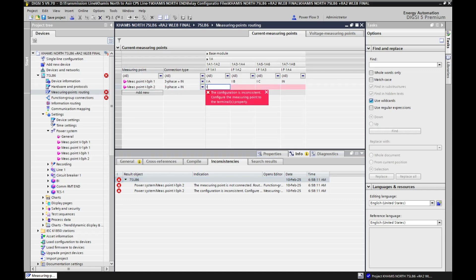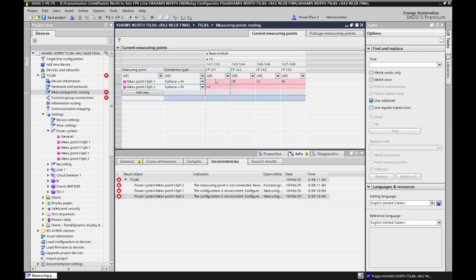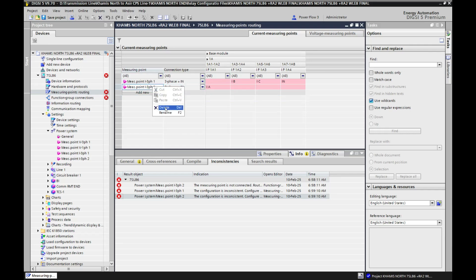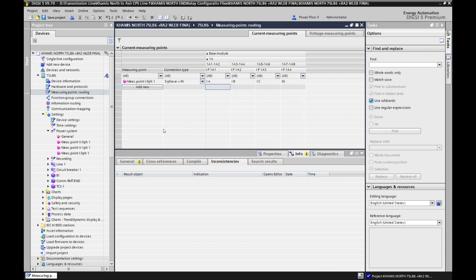Yes, because up to now we have not selected anything for the new measuring point. If I select Ia — but Ia is already assigned — so I try Ia for the new one. Now Ia has moved from the original location to here, but the error is still there because we cannot have two CTs sharing the same terminal. The red phase CT, whether from this CT or the one above, will come to terminals 1A1 and 1A2. Two CTs cannot come to the same terminal. That is why the error is coming. So we need to delete this second measuring point. I reassign Ia back, and as you can see the error disappears.